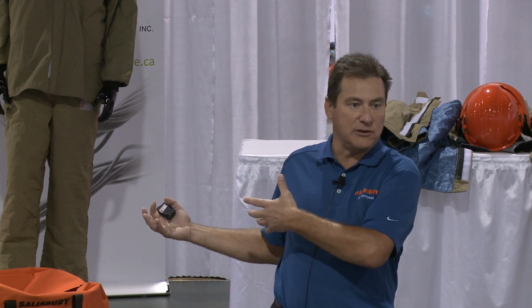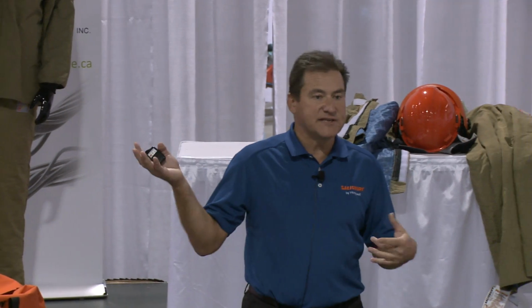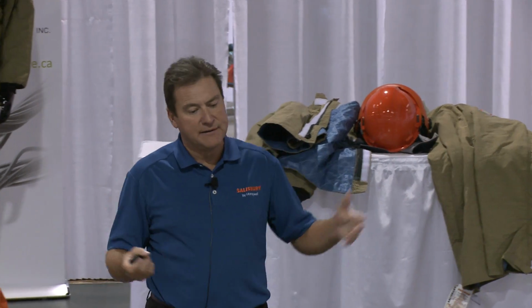There are two different methods of determining the rating you need for arc flash clothing. One is an engineered calculation. Lineman Testing Laboratories are here today, right at the next booth close to us, and you can get an entire engineered service done. Or you can use what we call task tables, which you find in the standards. The task tables indicate the type of task you're doing, the amperage, and the voltage, and it'll tell you the hazardous category, for instance category 2.